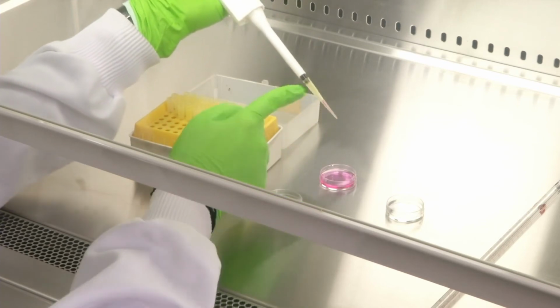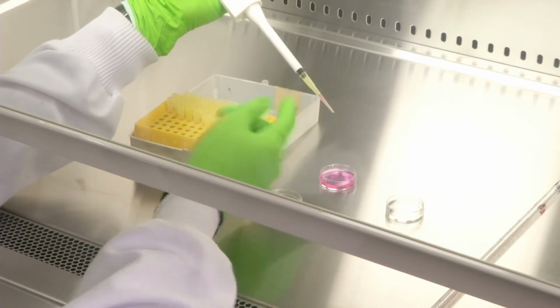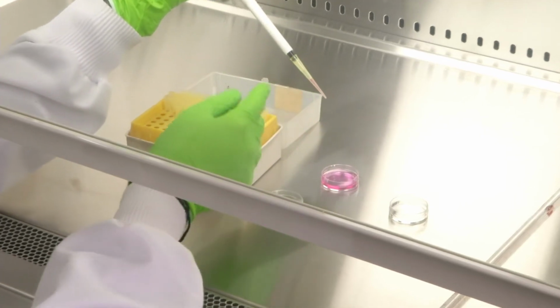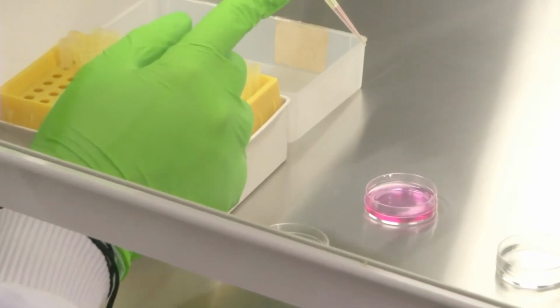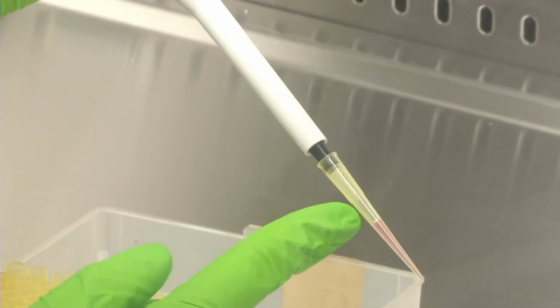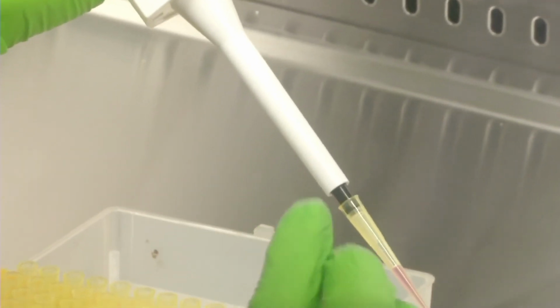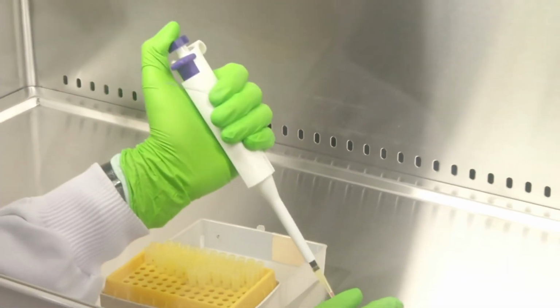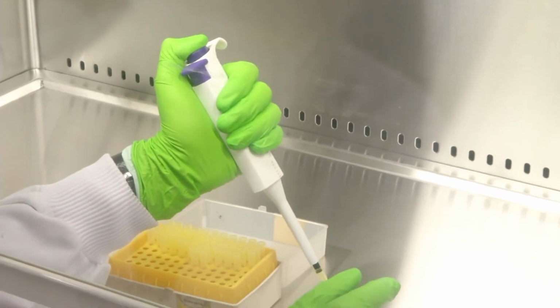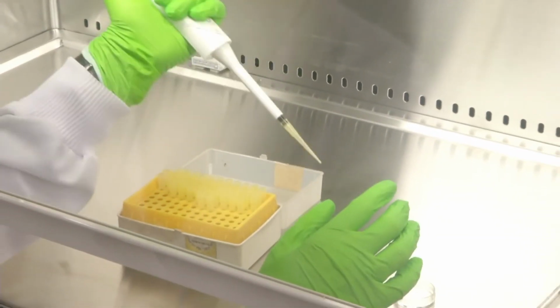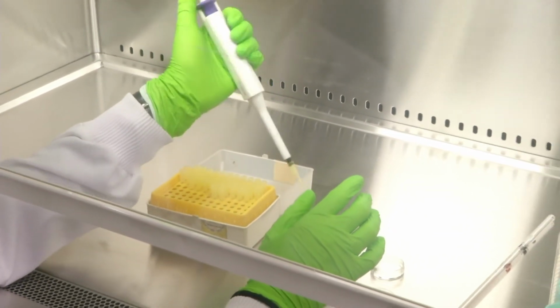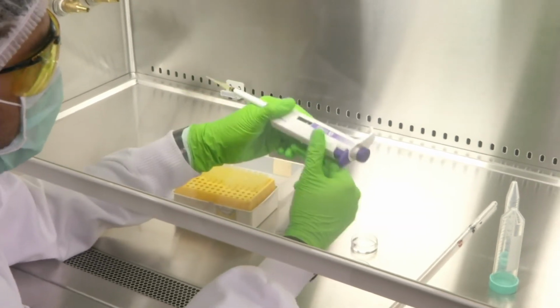As you can see, 100 microliters had come till here. This ring is there, no? Till that ring it had come. 200 microliters had come till here. Now 50 microliters has come only till here. So we do not have to worry about how much volume to take; we just need to set it here. The liquid also will not flow out. Unless we press it and drop it, it will not go away. It will stay inside the tip. Now let me take it back to 100 microliters.